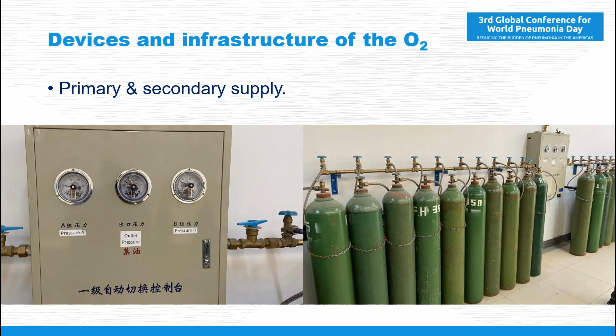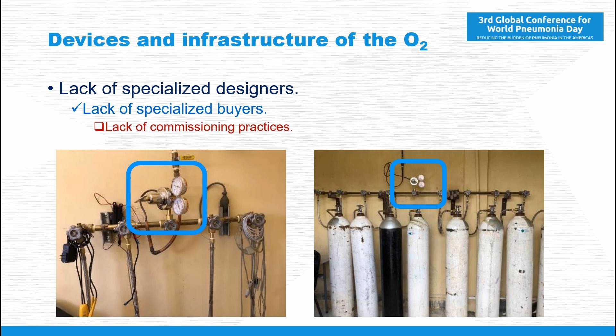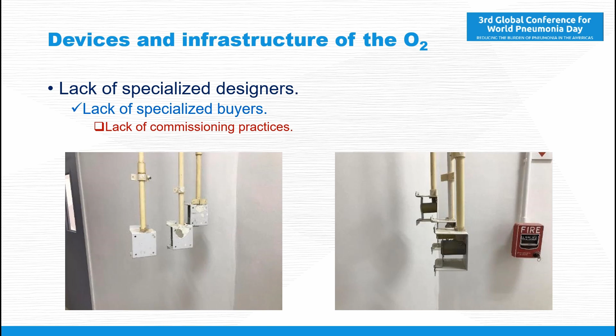We have to improve the process of commissioning. One company does the design, another company does the installation, and another company or the engineering of the hospital does the commissioning. Working with specialists can reduce this type of risk. It's also possible to find oxygen pipelines constructed using plastic tubes inside copper tubes. You can also find medical compressed gas using plastic pipelines. It's important to understand that medical air is used along with oxygen or nitrous oxide in anesthesia machines or mechanical ventilators.